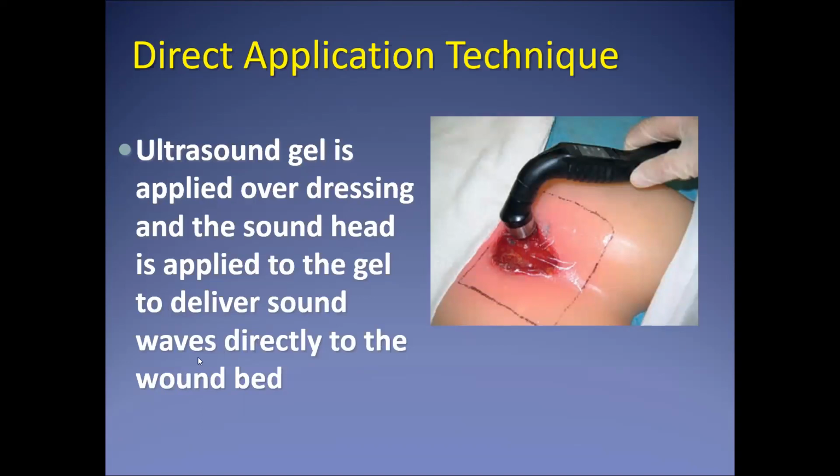But we're going to do a pulsed ultrasound over the area. That means the head's going to be on and off at whatever rate that pulsed is. So if I do a 20% ultrasound, that means that ultrasound head's only going to be on 20% of the time and off for 80% of the time. So it's going to deliver a refracting pattern that's actually driving those cavitation waves a little bit to help with healing.